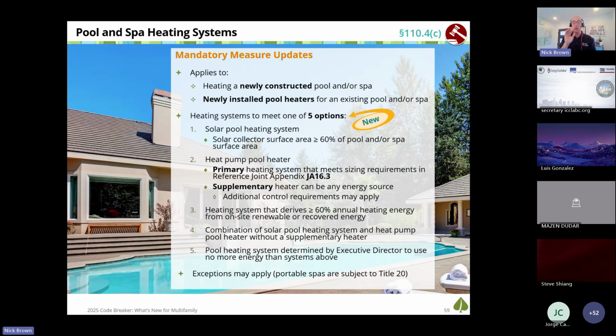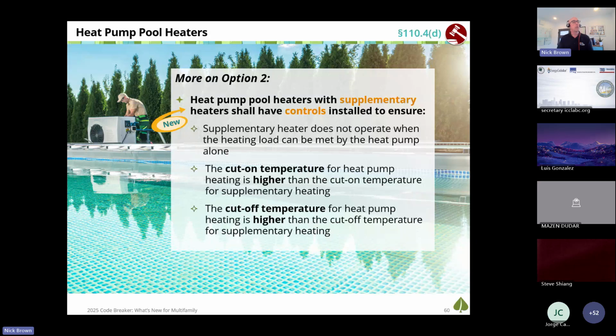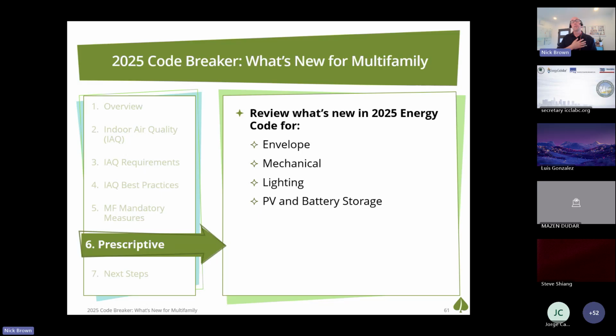And when I worked this pool and spa show last year, contractors were saying, wow, I need to pull more power to that pool subpanel than I did in the past if it's going to serve a heat pump pool heater instead of gas. Now, if we have supplementary electric resistance heat as part of this system, they need to be controlled such that they don't operate when the heat pump can manage the load alone. The cut-on temperature for the heat pump is higher than for the supplementary heating system, and the cut-off temperature for the heat pump is higher than the cut-off temperature for the supplementary system. So just like in HVAC, mechanical systems, there's new energy code requirements on supplementary resistance heating to make sure it doesn't eat too much into the savings of the heat pumps.